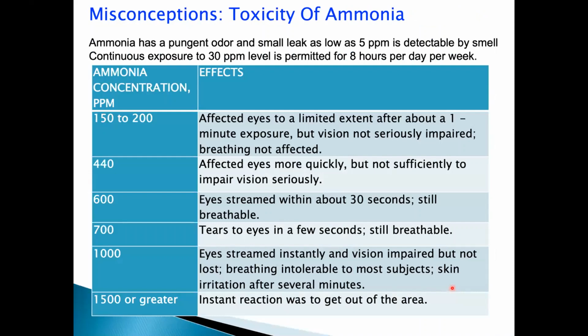Then toxicity. Yes, ammonia is a toxic gas and it may have harmful effects on the human body, but it has a pungent odor. So if we have ammonia as low as 5 ppm, it can be very easily detected by the human nose. Internationally, and also now in India, the TWA value is 30 ppm. It means if you are working in an ammonia environment with 30 ppm leakage, you can work for 8 hours and there will not be any effect on you.